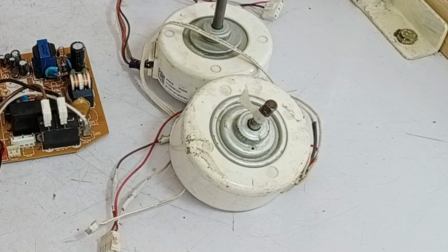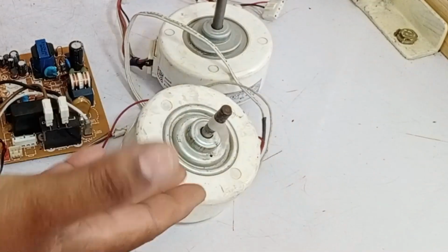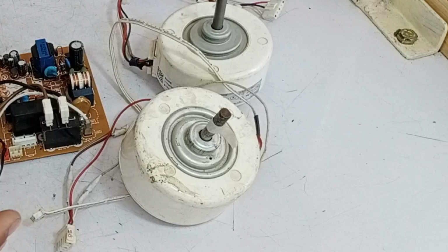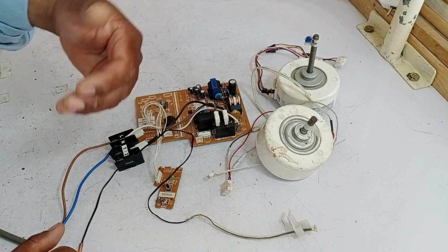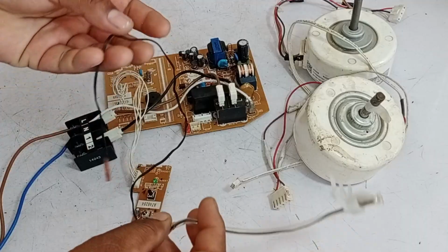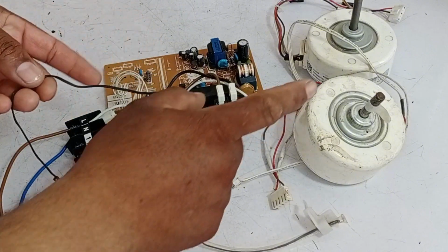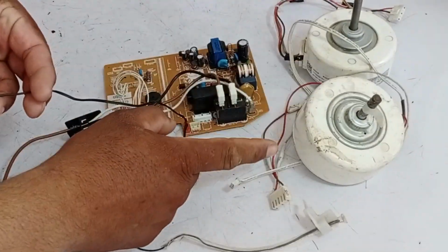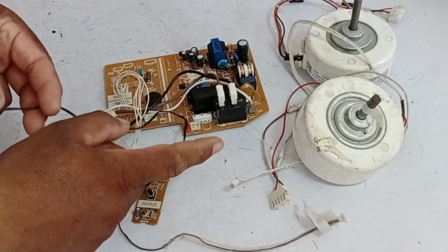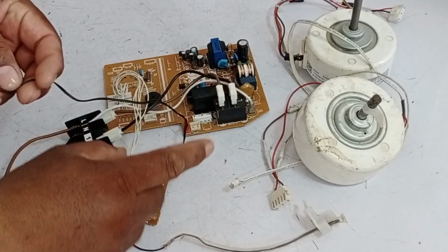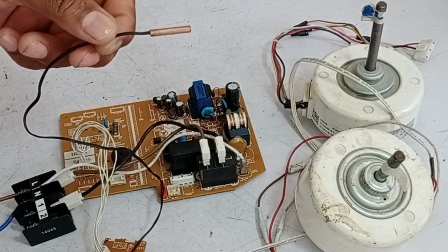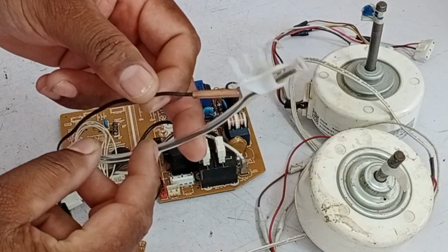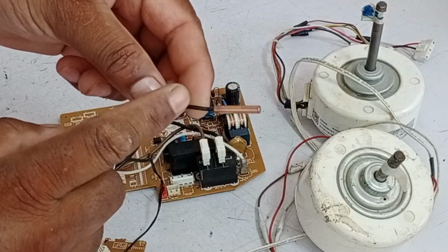When there's a motor issue, it's usually easy to detect because the motor will stop running, the unit won't operate, and there will be no output. Without output, the compressor won't start, so you can identify a motor fault easily in this way. However, if the sensors are faulty, the motor might still run. As long as the feedback is correct, the motor is functioning properly and it's not jammed. In this case, the issue is likely with a sensor, and often it's the pipe coil sensor that goes bad. Although the room sensor can also fail, it's less common. The pipe coil sensor failure is more likely.